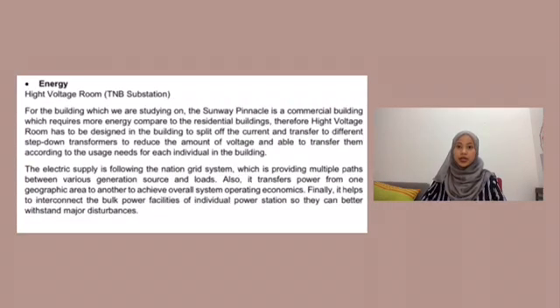Energy. The Sunway Pinnacle is a commercial building which requires more energy compared to the residential buildings. Therefore, high voltage room has to be designed in the buildings to split off the current and transfer to different step down transformers to reduce the amount of voltage and able to transfer them according to the usage needs for each individual in the buildings. Also, it transfers power from one geographic area to another to achieve overall system operating economics. Finally, it helps to interconnect the bulk power facilities of individual power stations so they can better withstand major disturbances.